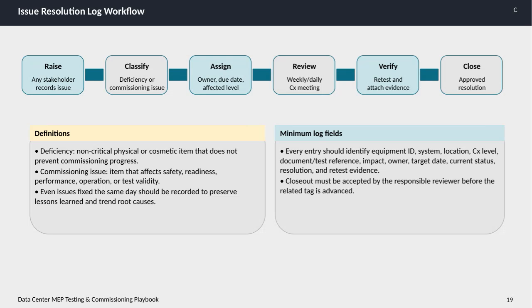Here, we have the issue resolution log workflow, which is a critical part of our data center MEP testing and commissioning process. The workflow begins with any stakeholder raising and recording an issue. This is important because it ensures that no concerns go unnoticed. Once an issue is logged, we classify it as either a deficiency or commissioning issue. A deficiency is a non-critical, physical, or cosmetic item that won't stop the commissioning progress, while a commissioning issue is more serious and affects safety, readiness, performance, operation, or test validity.